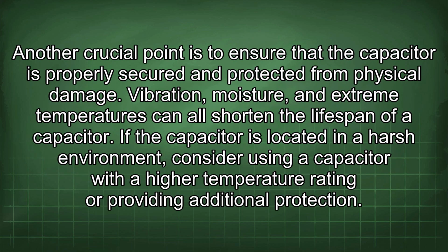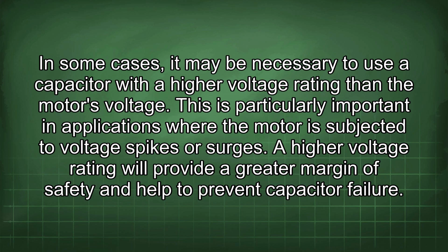Another crucial point is to ensure that the capacitor is properly secured and protected from physical damage. Vibration, moisture, and extreme temperatures can all shorten the lifespan of a capacitor. If the capacitor is located in a harsh environment, consider using a capacitor with a higher temperature rating or providing additional protection. In some cases, it may be necessary to use a capacitor with a higher voltage rating than the motor's voltage. This is particularly important in applications where the motor is subjected to voltage spikes or surges. A higher voltage rating will provide a greater margin of safety and help to prevent capacitor failure.